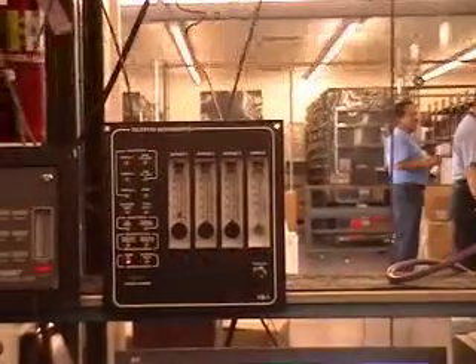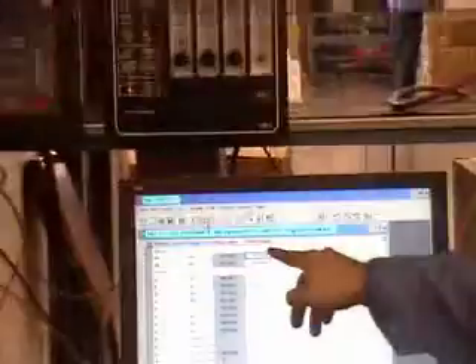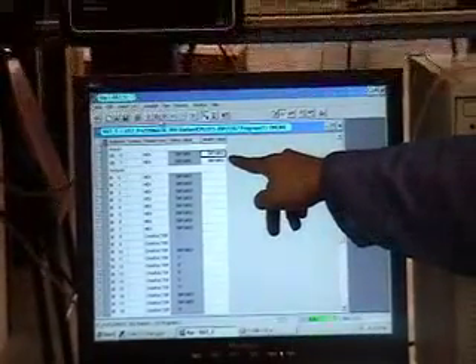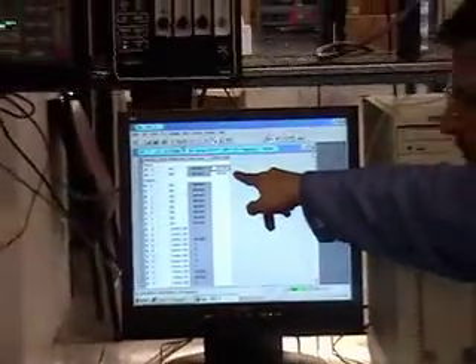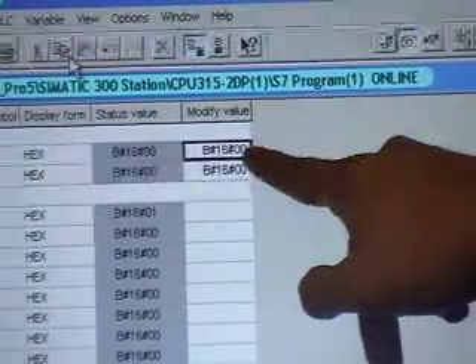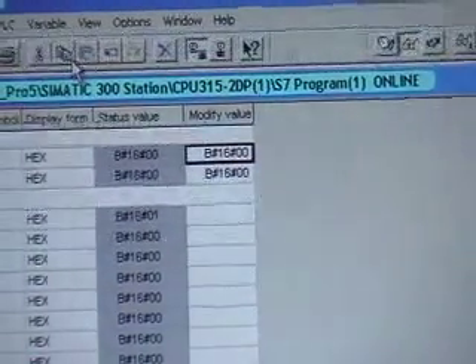The first thing we're going to do is send a command to turn on the sample 1 valve. The first valve, we're going to turn it on. By sending a command on the first address, QD0 is the first address, we are going to send a command. And the command is number 1. Number 1 is for sample 1.